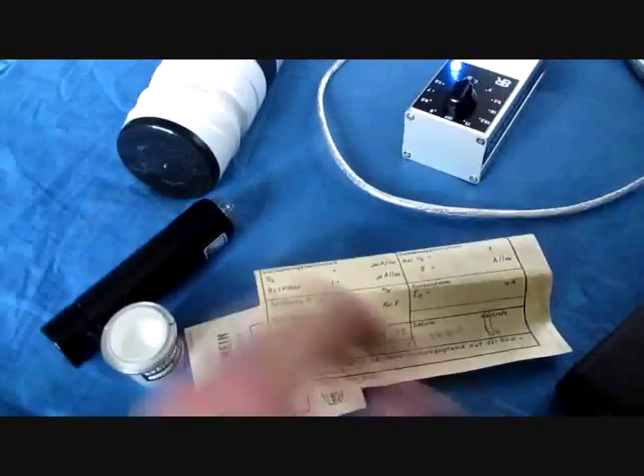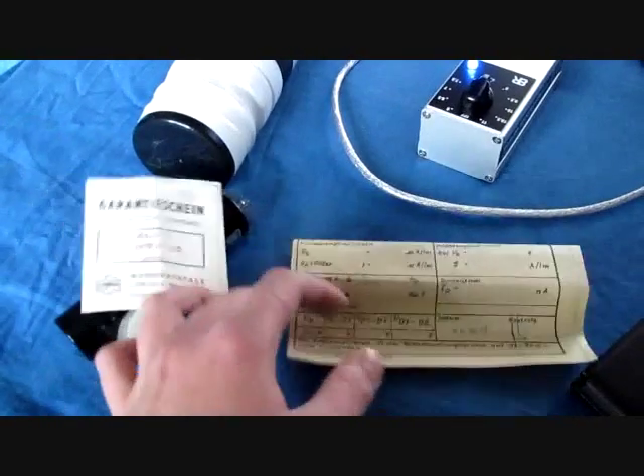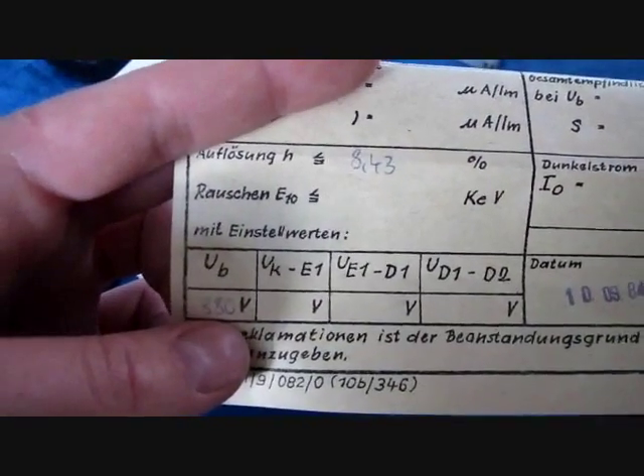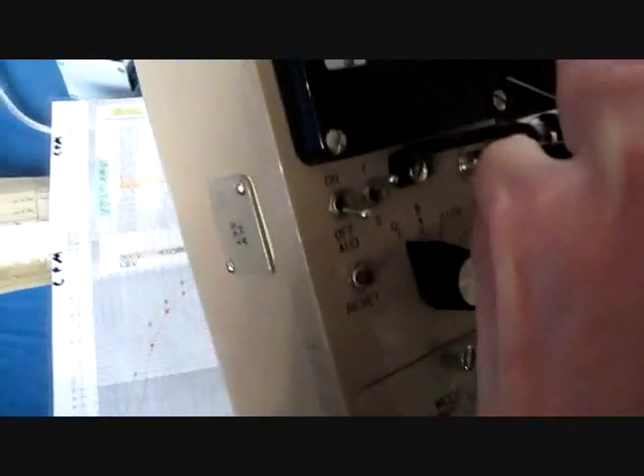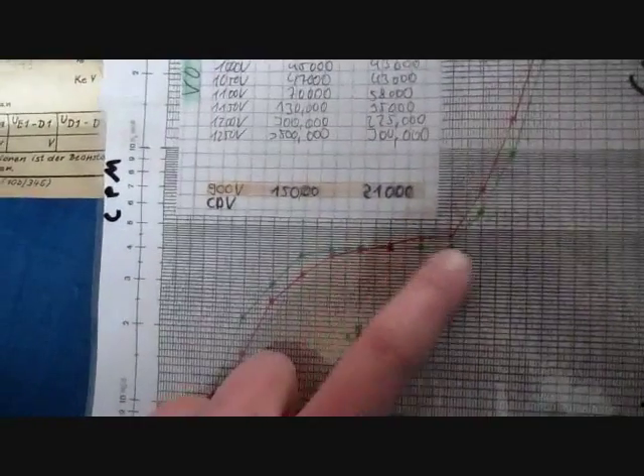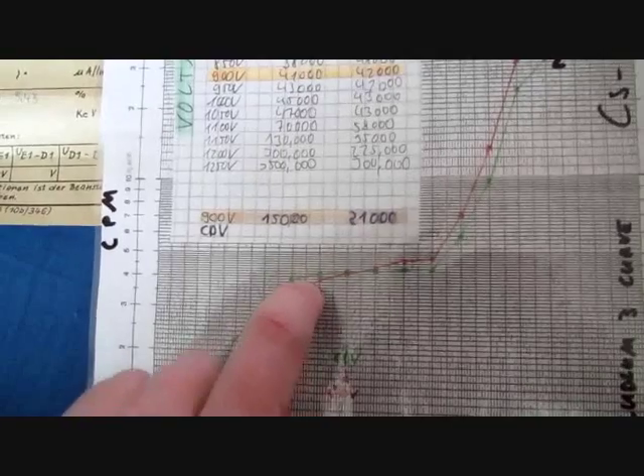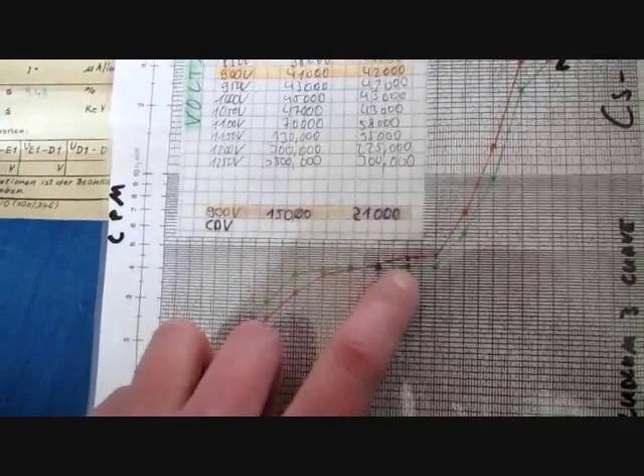As for the operating voltage, maybe you have a nice manual with your scintillation counter that says something about that. Like here it says 880 volts for the photomultiplier. So either you can use that, or you can just use the free software for gamma spectroscopy, we'll talk about that later. Or you can actually do a proper curve. That is, you connect the scintillation counter to, for example, a Ludlum or something else that you have, or just use the software on the computer. Then you adjust the high voltage in steps of 50 volts, and you should be left with an increasing gain, like this. And then you will get a shoulder, a plateau, where the counts don't drastically increase anymore, even if you increase the voltage in steps of 50 volts.